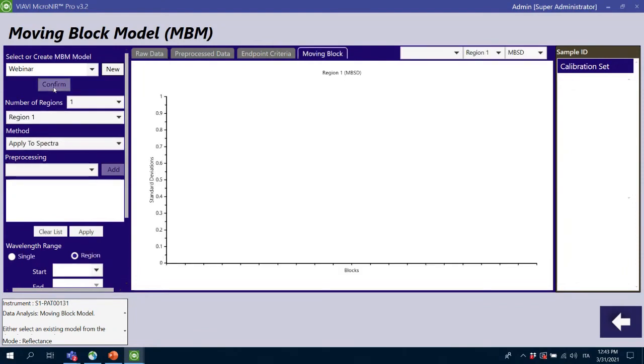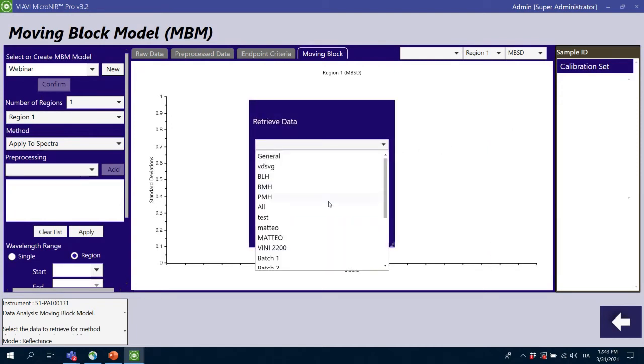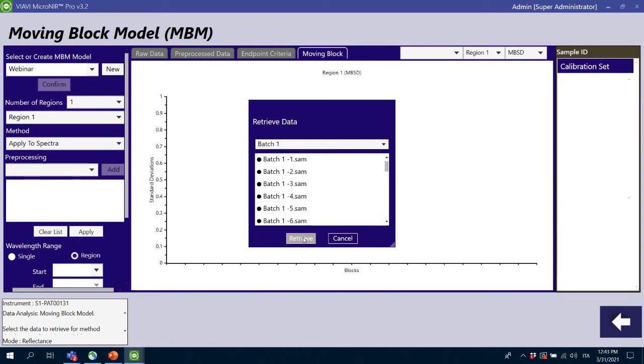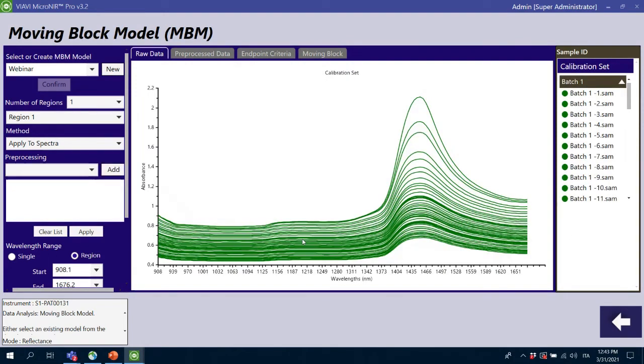We need to confirm the method, and afterward, on the right hand side of the screen, there is this box with the calibration set. We need to upload the first list of spectra. In this case there are 50 spectra acquired at different times. It's not a blending, it's an evaporation, but the considerations that we can get are exactly the same. Here you have the setup. We are working with only one region, meaning that we are considering from 908 to basically 1700 all the wavelengths of our spectrum. Eventually, we can also define specific regions for specific peaks, but let's keep it simple.